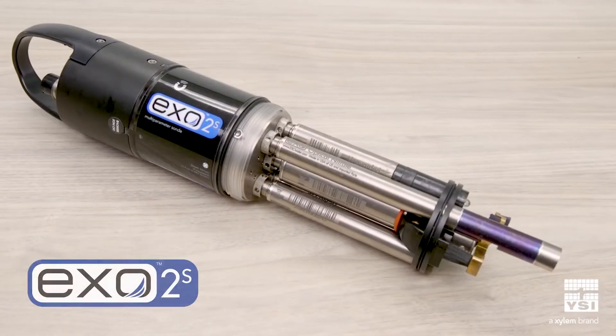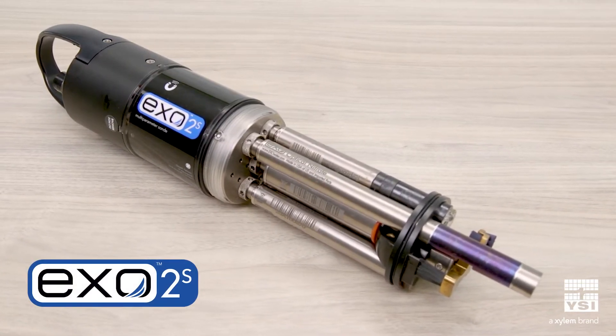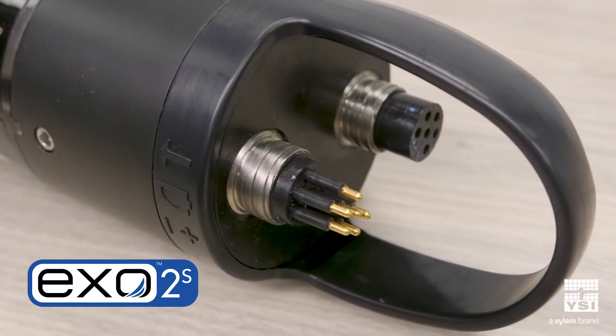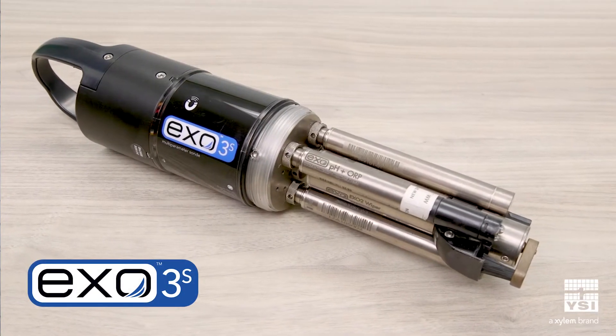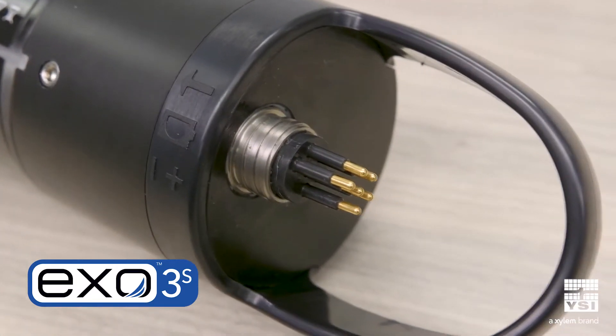The EXO2S features seven ports including a central wiper port to keep sensors clean during deployments. It also includes an auxiliary port for integrating third-party sensors or daisy-chaining sondes together. And if you don't need that many ports but still want active anti-fouling, then the EXO3S is just right with five ports including the central wiper port.